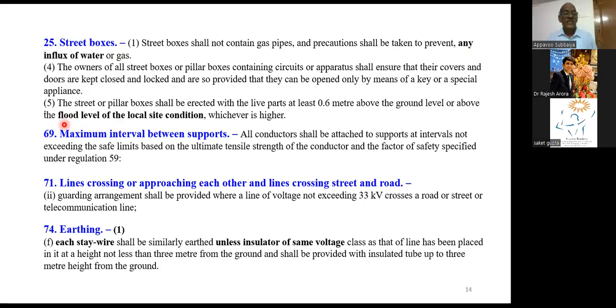Another thing, maximum flood level. And this is one important maximum interval between poles. Previously, for the 11 kV, for example, it was estimated. Now it is specifically provided, even less than 60 meters, depending upon the wind conditions prevailing during the monsoon season, and the size of conductors and the pole sizes.